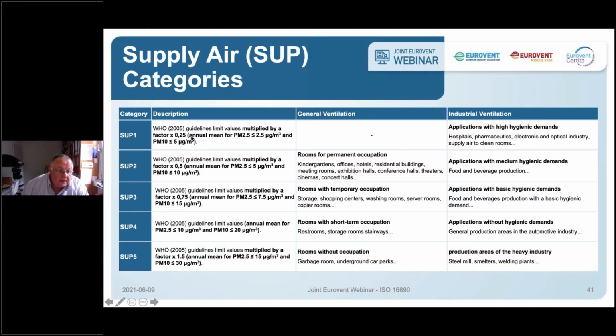And for the cleanest supply air quality, the WHO guideline values are multiplied by a factor of 0.25. General ventilation, of course, should be or can be the same. In the industrial field, we have hospitals, pharmaceutical production, electronical and optical industry, and supply air to clean rooms. Just to mention, we also have defined a supply air quality 5, where the WHO guideline values are multiplied by a factor more than 1.5. These are rooms without occupation, garbage rooms, underground car parks, or production areas in heavy industry like steel mills, smelters, and welding plants.